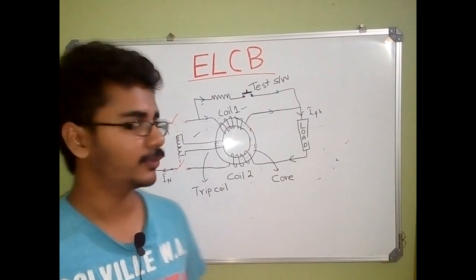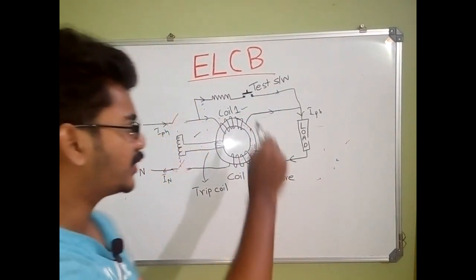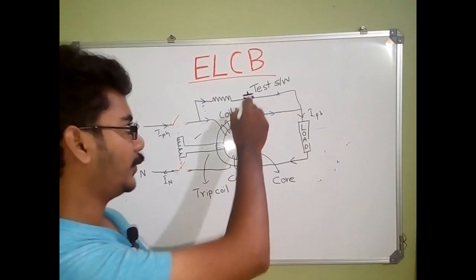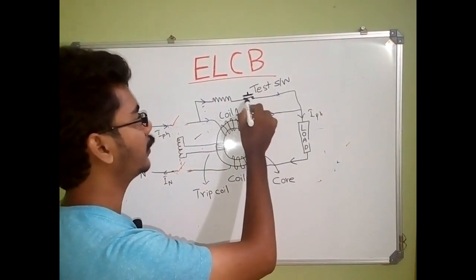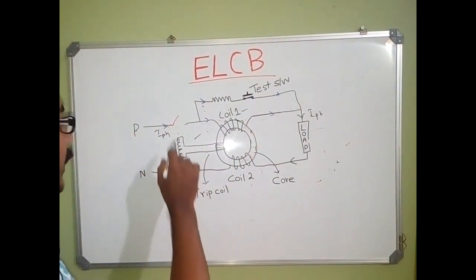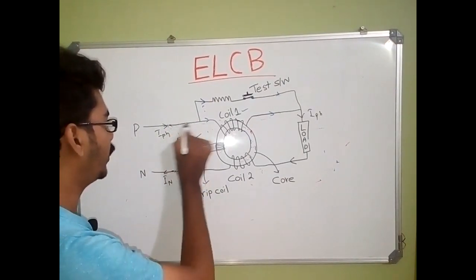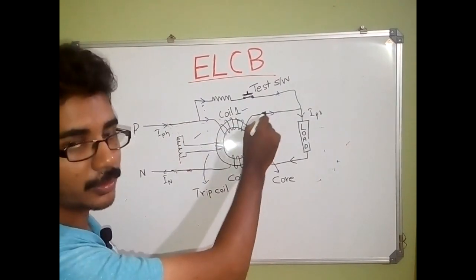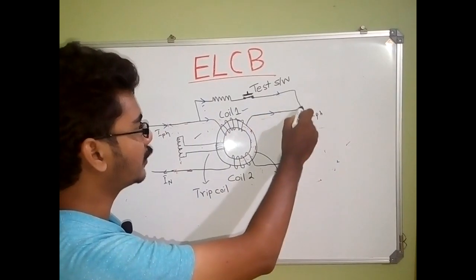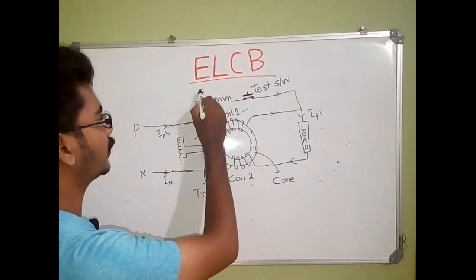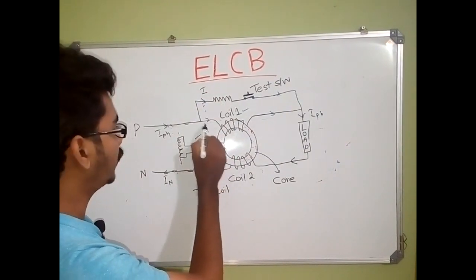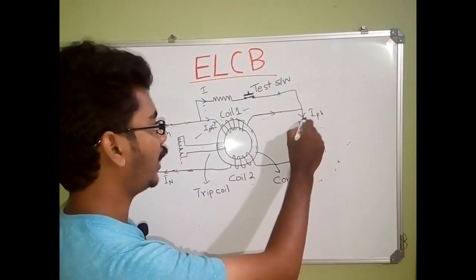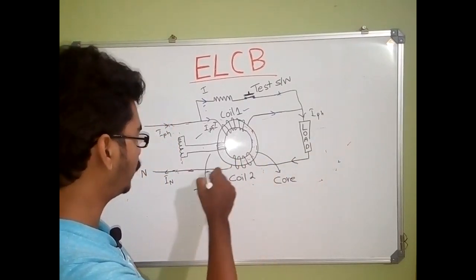Now we are going to look at the function of the test switch. The test switch is used for testing whether the ELCB is in working condition or not. When we press the test switch, this branch will be short-circuited. Under normal conditions, the phase current entering is split into two branches — one passes through Coil 1 and the other passes through a resistance and this terminal. Let us say the current through the test switch is I, so the current through Coil 1 is I-phase minus I.